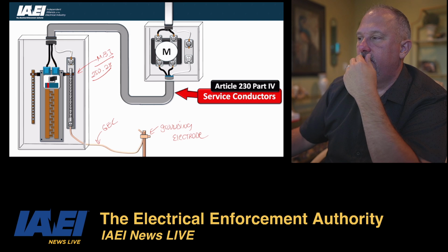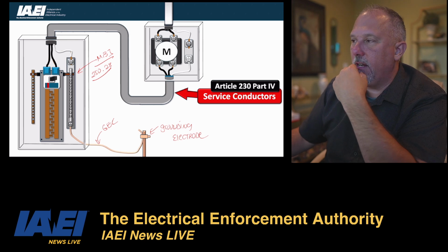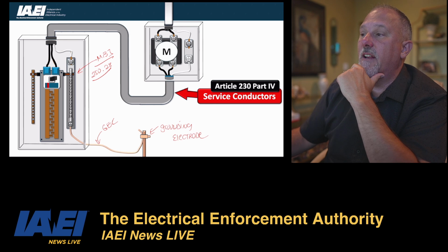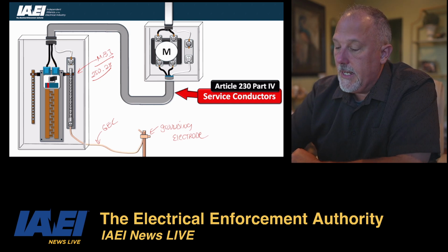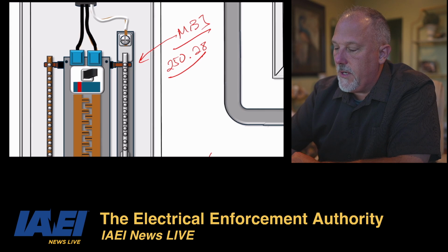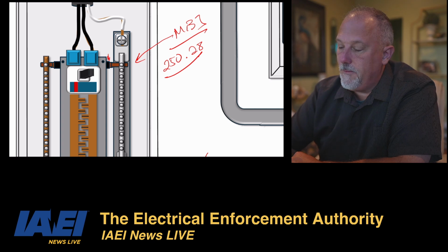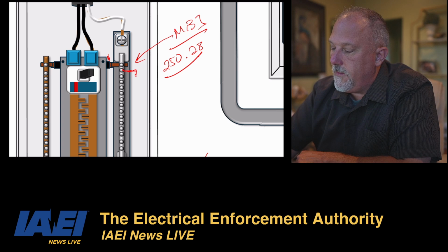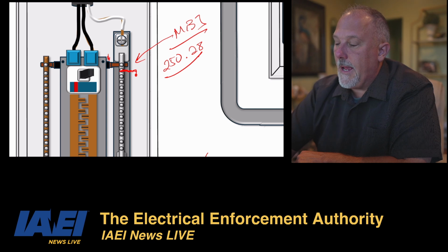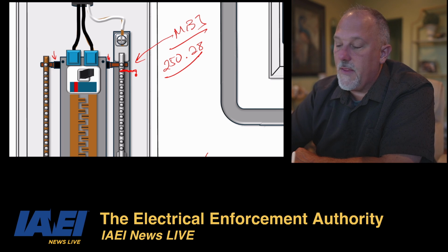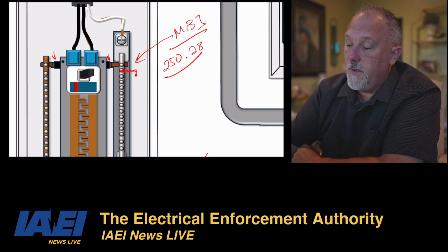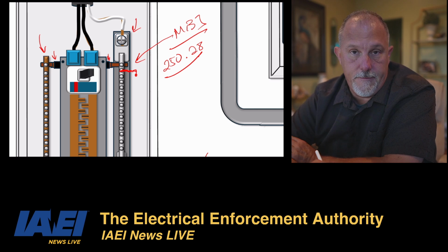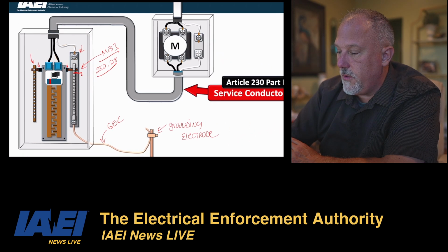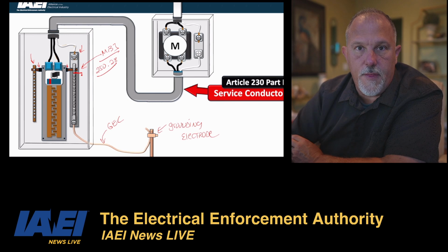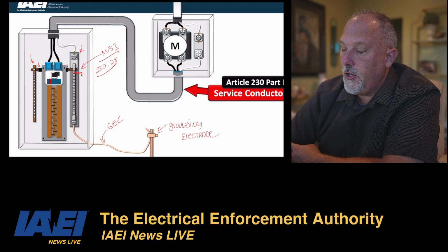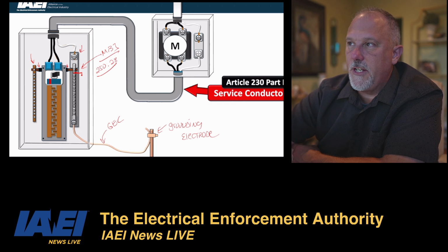This tells you if the main bonding jumper is a screw only, the screw has to be identified with a green finish that shall be visible with the screw installed. And how you may see that, this bar would not be there. You would just have a green bond screw that goes in this way. Now, if you had that and this bar that physically connects the ground bar with this neutral bar was not there, then the grounding electrode conductor would have to land on that neutral bar. You can't use the back pan as your main bonding jumper.